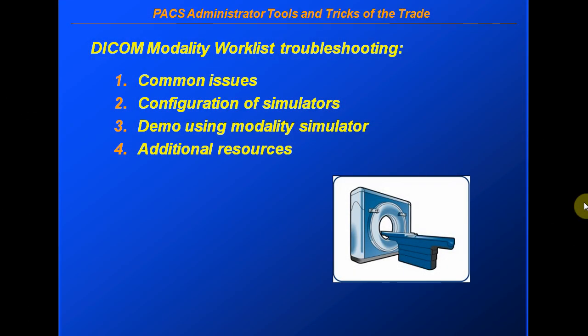Hello, this is Herman Osterwick and in this presentation we're going to talk about how to troubleshoot the DICOM modality worklist. The DICOM modality worklist is the mechanism by which a modality such as a CT, MRI, ultrasound, or any digital modality that wants to talk to the information system would pull back the worklist that the technologist would use to select the right patient demographics, ordering and scheduling information.